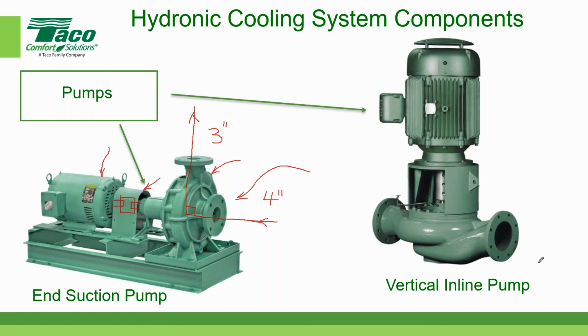The other category is called vertical inline, and as the name implies, it's inline with the piping system. This is the suction side here, so there's the pipe that comes in the suction, there's the discharge, and one of the major characteristics of an inline pump is that the suction and the discharge are the same size. So if this suction happens to be 4 inches, the discharge would also be 4 inches. And that's characteristic of all inline pumps. As the name implies, it's in line with the piping system. You can almost think of it this way: if you cut the pipe here and here, then you can mount the pump between those sections of pipe.